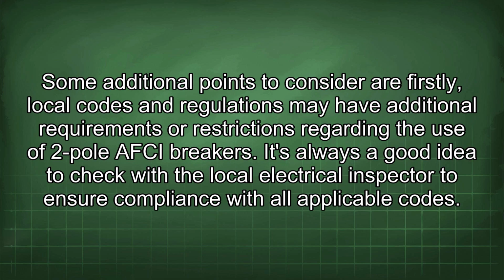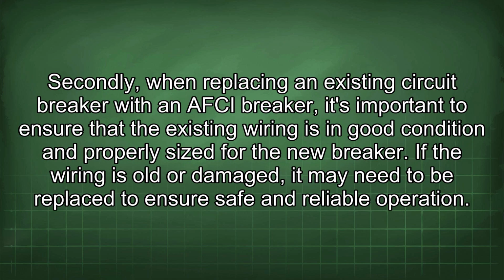Some additional points to consider are, firstly, local codes and regulations may have additional requirements or restrictions regarding the use of two-pole AFCI breakers. It's always a good idea to check with the local electrical inspector to ensure compliance with all applicable codes. Secondly, when replacing an existing circuit breaker with an AFCI breaker, it's important to ensure that the existing wiring is in good condition and properly sized for the new breaker. If the wiring is old or damaged, it may need to be replaced to ensure safe and reliable operation.